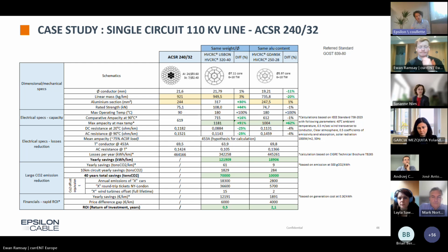conditions. So what do we have there? We have a solution, an advanced conductor with composite core, which has been rolled out all over the world for more than 20 years and is field proven. It answers the need of both distribution and transmission networks, and can be deployed in a very quick way without additional effort, because I need to mention that we are using exactly the same installation procedure as standard conductor, and the same type of fittings to attach those conductors onto the structures. Therefore we can quickly deploy this solution and double the capacity of the line.